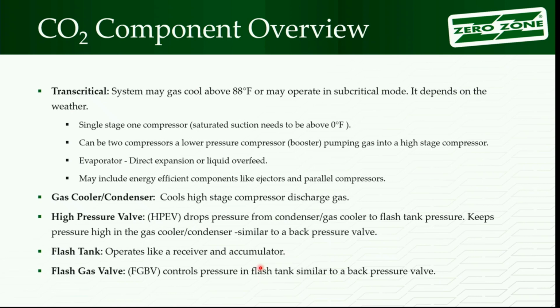Compressors: you could have a single stage compressor, one compressor. Compressors typically only operate down to about 0 degrees saturated suction. After that, the compressors don't have the structural capacity or discharge temperature to be able to function, so they're not out there, you can't get them. Something to keep in mind: if you get below 0 degrees, you're going to have a booster compressor. If all you ever did was commercial work, grocery stores, they always want what? Ice cream cold. It's always going to be below 0 degrees when you're working with it.